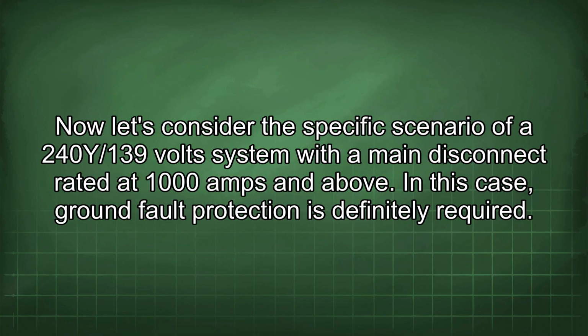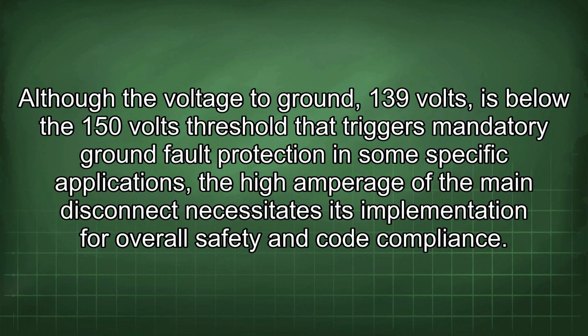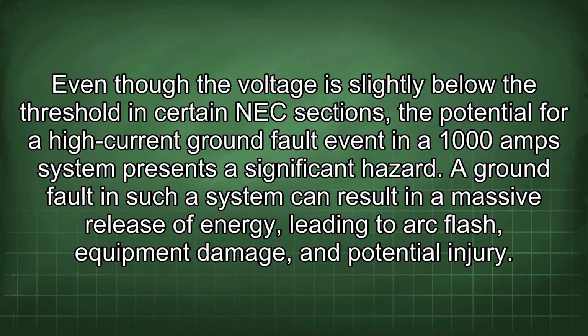Now let's consider the specific scenario of a 240Y/139 volt system with a main disconnect rated at 1000 amps and above. In this case, ground fault protection is definitely required. Although the voltage to ground, 139 volts, is below the 150 volt threshold that triggers mandatory ground fault protection in some specific applications, the high amperage of the main disconnect necessitates its implementation for overall safety and code compliance. Even though the voltage is slightly below the threshold in certain NEC sections, the potential for a high current ground fault event in a 1000 amp system presents a significant hazard.